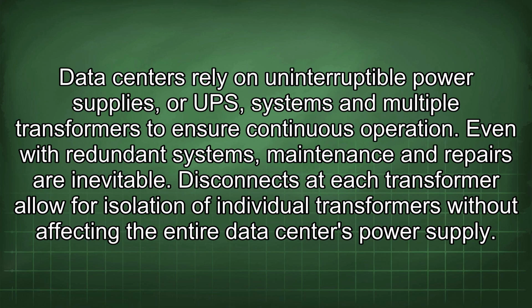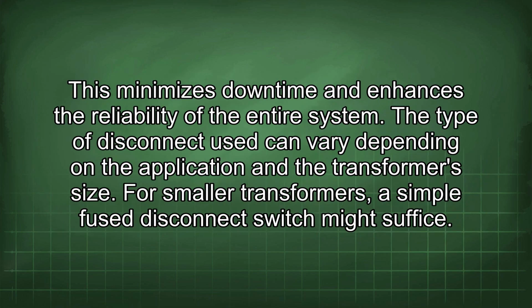Data centers rely on uninterruptible power supplies, or UPS, systems and multiple transformers to ensure continuous operation. Even with redundant systems, maintenance and repairs are inevitable. Disconnects at each transformer allow for isolation of individual transformers without affecting the entire data center's power supply. This minimizes downtime and enhances the reliability of the entire system.